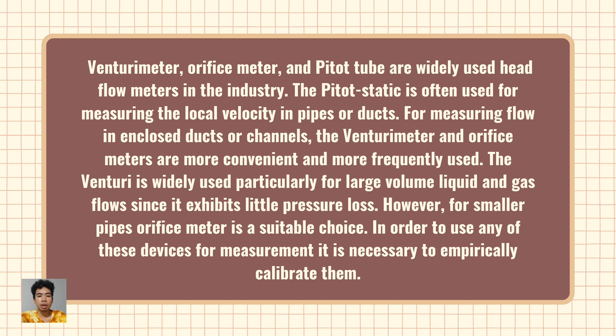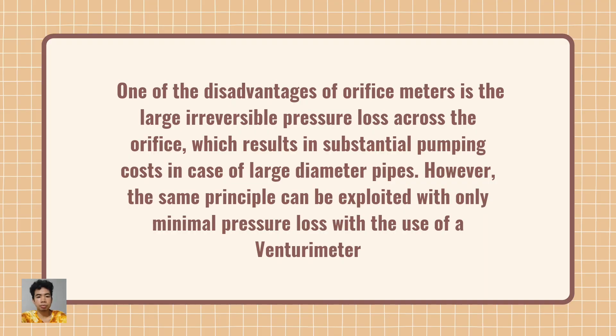However, for smaller pipes, the orifice meter is a suitable choice. In order to use any of these devices for measurement, it is necessary to empirically calibrate them. One of the disadvantages of the orifice meter is the large irreversible pressure loss across the orifice, which results in substantial pumping costs in case of large diameter pipes.